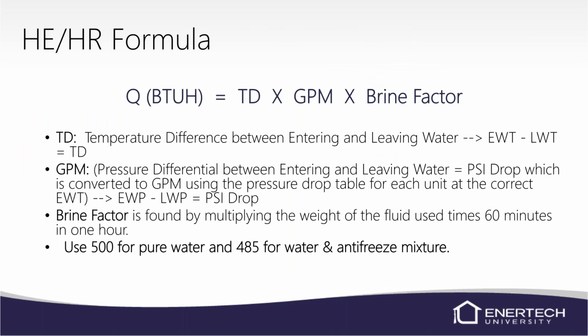The heat of extraction, heat of rejection formula. Basically it's temperature TD, which is the temperature difference between your entering and leaving water temperature. Your GPM, which is found from the pressure difference between your entering and leaving water, converted to GPM using our manual. Times your brine factor. Brine factor, or your antifreeze factor, your fluid factor, it's called quite a few things. But that's basically found by multiplying the weight of the fluid times 60 minutes in an hour.